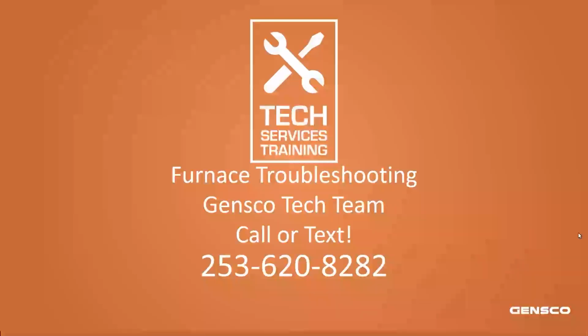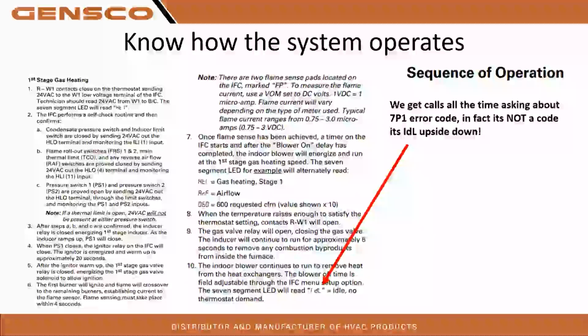So let's dig into it. Troubleshooting really starts at knowing the sequence of operation, what the expectation of that equipment is. All manufacturers kind of play by the same rules. We have the same settings because there are ANSI standards for how gas furnace operations and safeties work. So knowing the sequence of operation for equipment is where you start troubleshooting. What's the expectation?